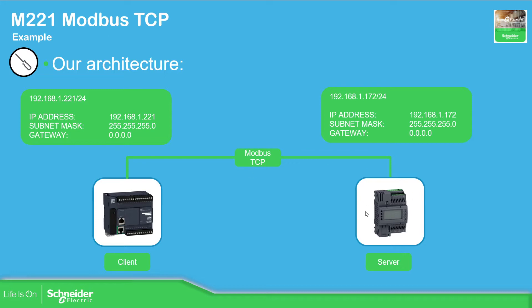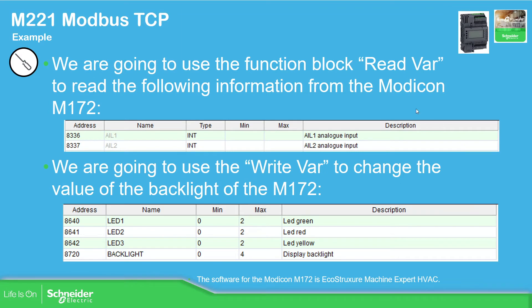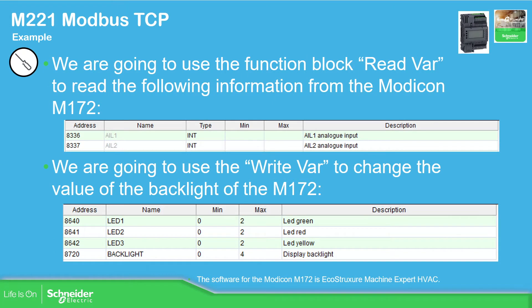The idea for this video is to communicate the Modicon M221 with another device. In our case, we're going to use the Modicon M172 via Modbus TCP. The M221 is going to be the client and the M172 will be the server. From the other PLC, this is exactly the same as we have done with Modbus serial, but instead we're going to use Modbus TCP. We're going to read the analog inputs and write into the backlight of the M172.